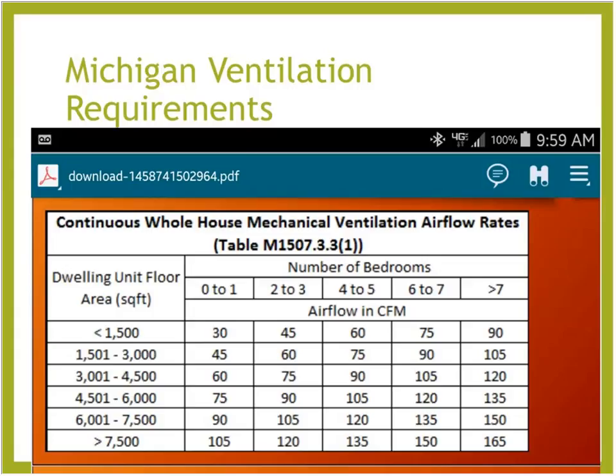Those above grade programs are LEED for Homes under LEED v4, and Energy Star version 3, to name two off the top, that actually require the airflow measurement, which is why I'm glad that you spent so much time on covering the install of these fans in the ductwork, because there's a lot of failures on meeting the flow requirements when ducts get pinched, or there's multiple bends in them, or excessive lengths, or any type of thing that impedes the flow of the air.